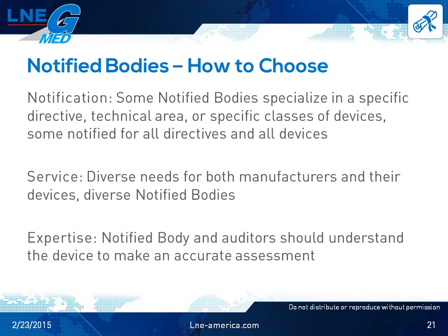First, make sure that the notified body is notified to the directive for the device you're using, and double-check that the notified body can perform the conformity assessment you need. Second, service. Notified bodies are diverse, just like medical device manufacturers, and so manufacturers have different needs from each other and need notified bodies that can offer them the best fit. As a result, make sure your notified body's customer service and service offerings fit you best so that you can have a real partner in your device's certification.